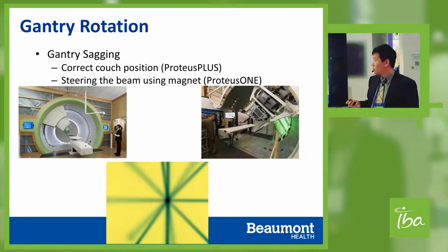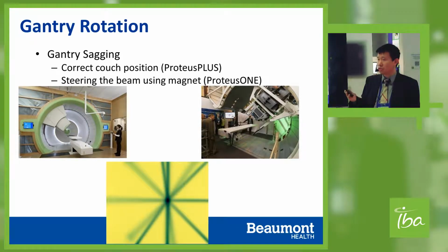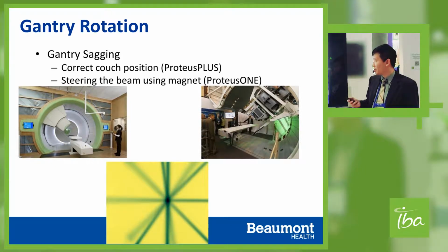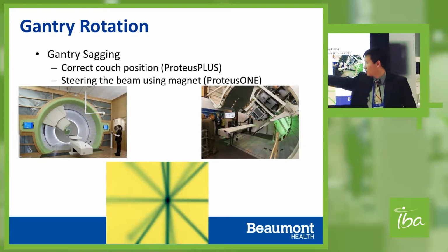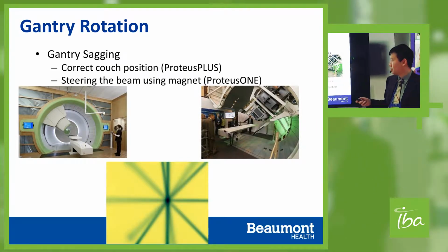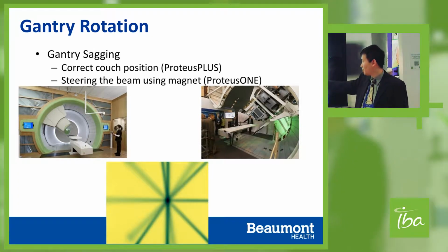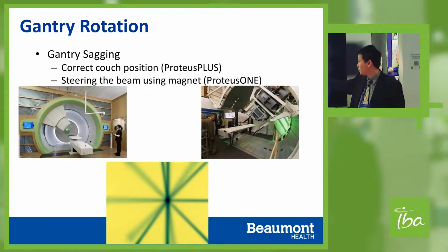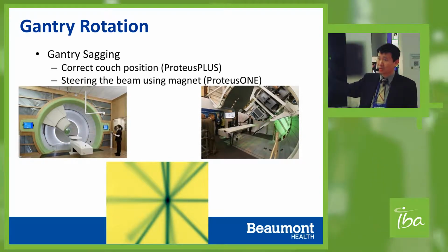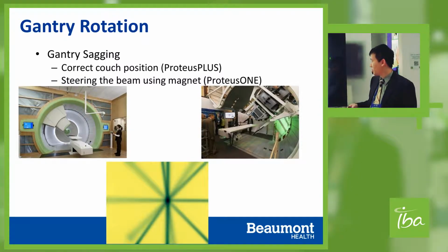So what's the most important part is the gantry rotation. As long as we know, the huge gantry of the Proteus Plus, you might have huge sagging, so you use the couch to correct that. The good part is you have an X-ray tube in the nozzle, so you can image the patients using beam's eye view. However, in the Proteus One, you don't have the X-ray tube in the nozzle, so you lose this critical component. However, to compensate, we have the flat panel drop in to have the volumetric cone-beam CT to compensate for the loss of the beam's eye view.